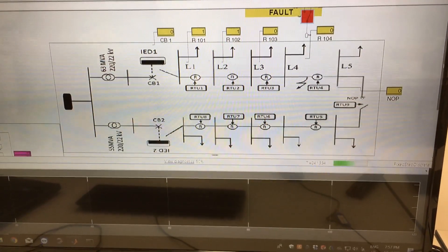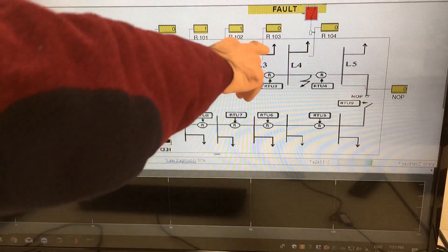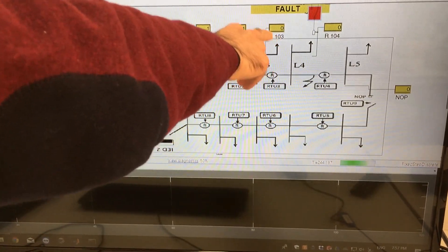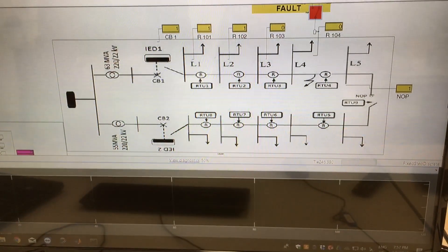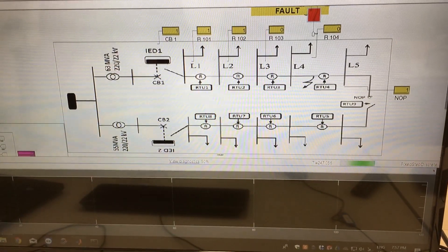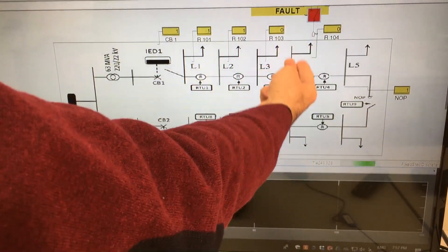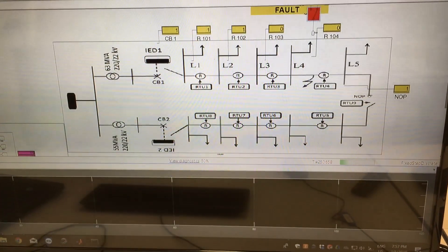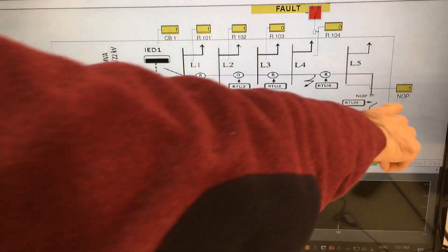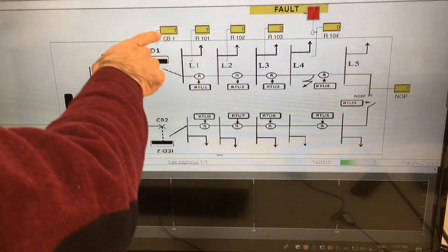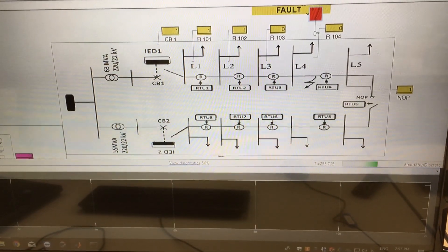The action that FDIR now takes is to open this recloser, and this is actually fault isolation — we isolate this segment of the circuit. The last action is to close back the normally open switch and the circuit breaker to restore the supply to the affected loads.